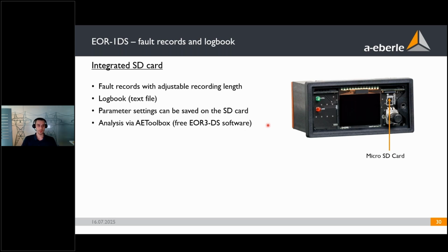For fault analysis, the EOR-1DS also has an integrated SD card. So you do have fault records with adjustable recording length saved on your SD card. You have a logbook as well. And as I said before, you can save your parameter settings on the SD card. And then afterwards you can analyze your fault records and your logbook using, for example, the Eberle toolbox, which is the free parameterization software of the EOR-3DS, but also of other devices.